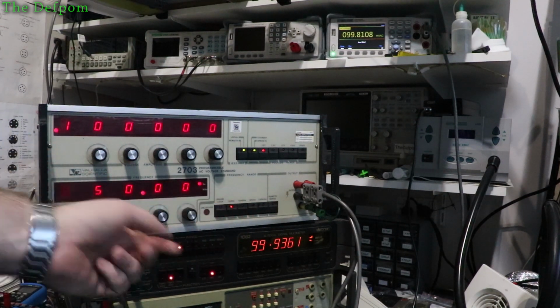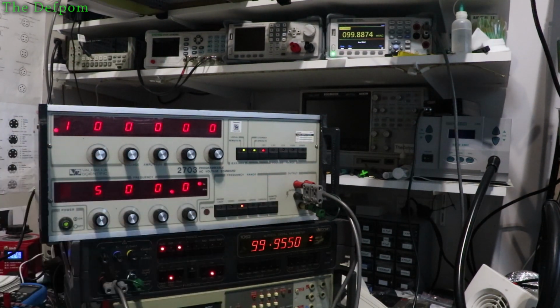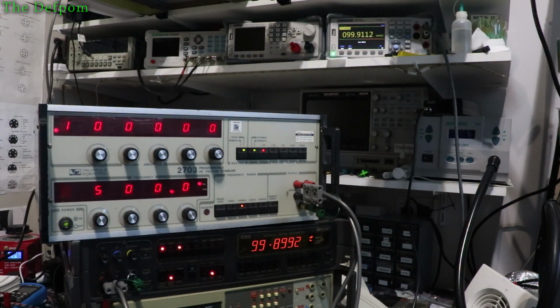The calibration on this is done at 500 Hertz, so I'll do that - 500 Hertz - and so that calibrated value there should be closer once it settles down. Here we go.